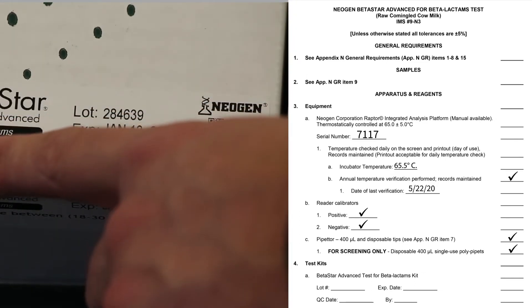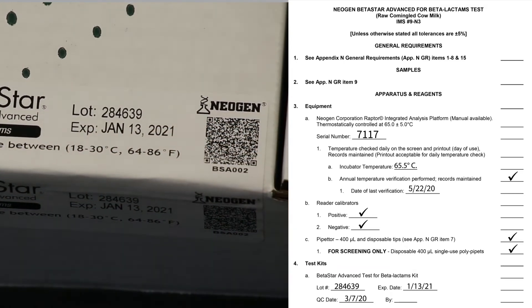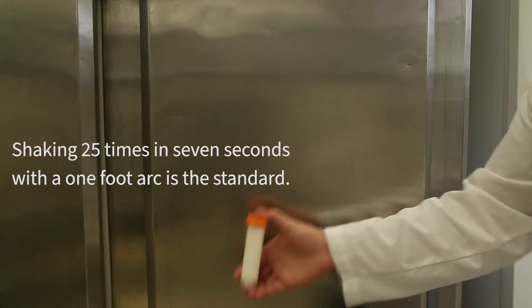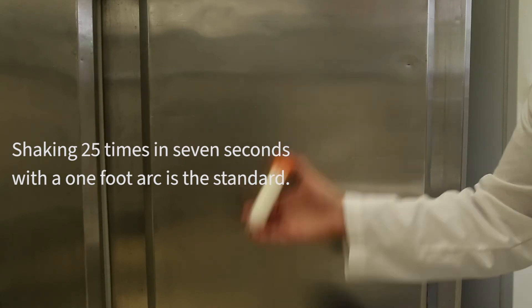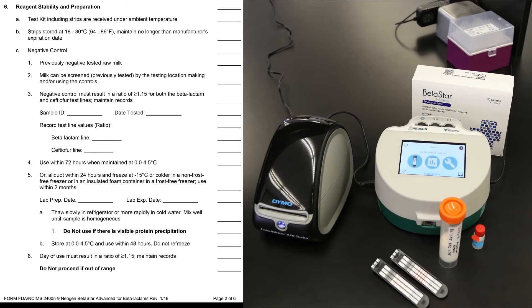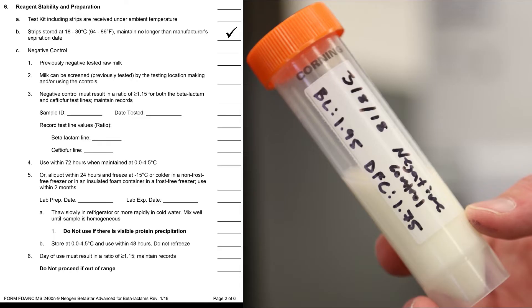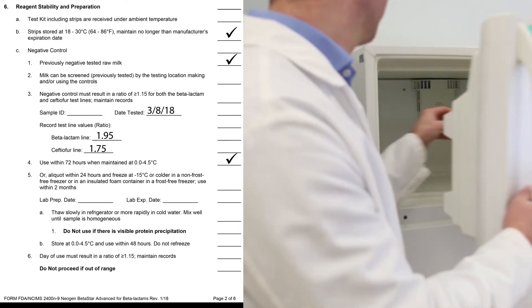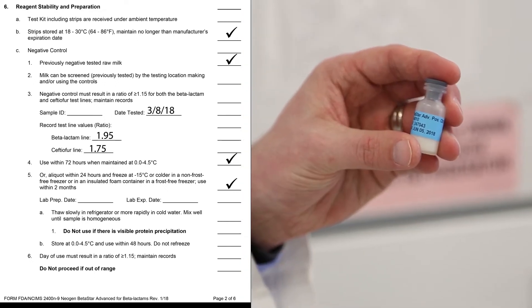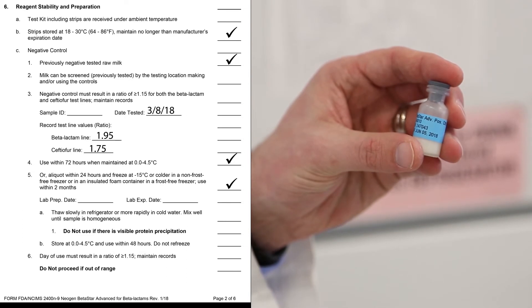Section 4 specifies the test kits, noting lot number, expiry date, QC date, and person responsible. Section 5 refers to both milk sample and positive-negative control mixing. Section 6 refers to reagent stability and preparation. Betastar Advanced tests are the only tests within the NCIMS Appendix N program that can be stored at room temperature. Daily performance checks require previously tested raw milk as a negative control. The negative control must be properly labeled with the numerical ratio and date tested, and must be used within 72 hours, or frozen controls can be prepared and used instead. Once frozen controls are thawed, they must be used within 48 hours.